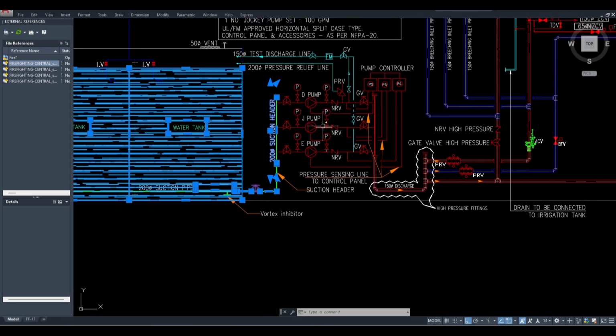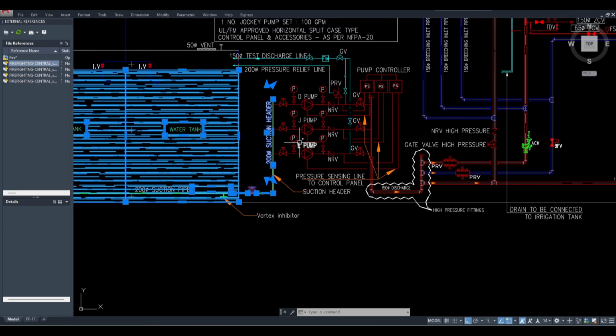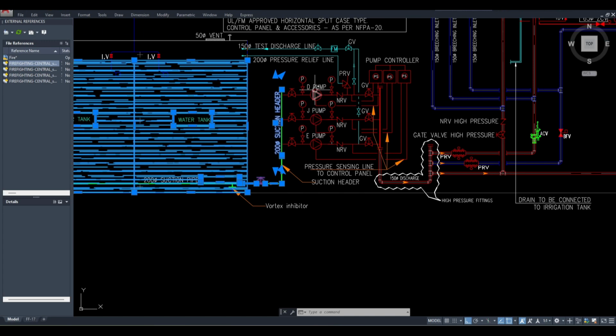Then you will be getting three kinds of pumps. Okay, first is the electrical pump, then the jockey pump, and then the diesel pump. Okay, so electrical pump, jockey pump and diesel pump. So basically what happens, this complete system after the pump, whatever is connected to the building lines, it has to be filled with water 24/7. It should always be ready with water. Okay, because you cannot know when the fire can happen in the building. So suppose this complete system is filled with water. That water cannot be only water. It has to be pressurized water. Okay, so all these lines are always pressurized with water.